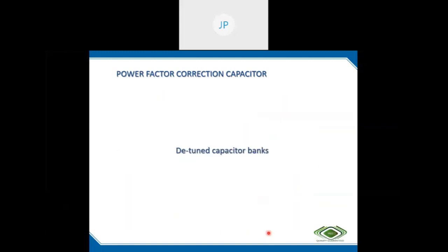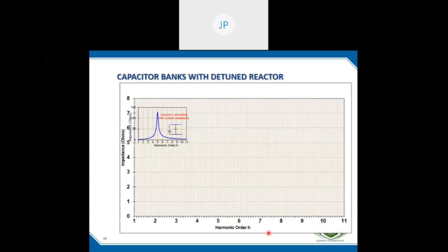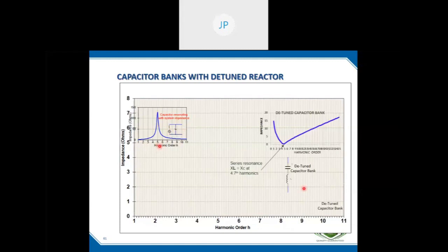So the remedies are: first, a detuned capacitor bank. You can see this is the resonating point of a particular system. Only a capacitor is connected to the system, so it will have a parallel resonance. This system is resonating at the fifth harmonic. So we provide a detuned capacitor bank. Detuning means we add a detuned reactor in series with the capacitor such that the tuning point will be less than this fifth harmonic resonating point. So here we select a 4.7 harmonic frequency to tune this circuit.